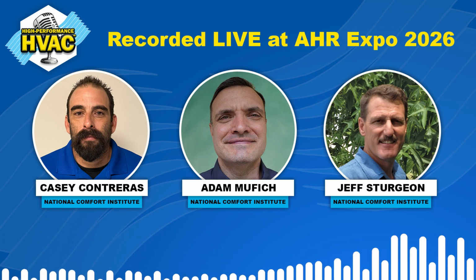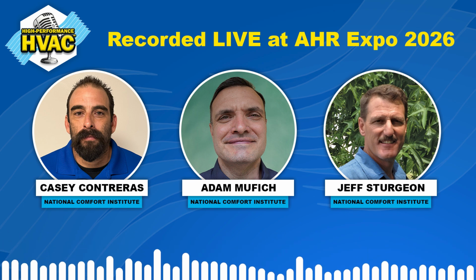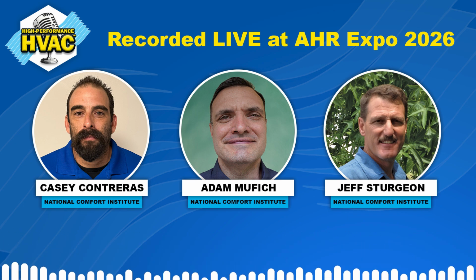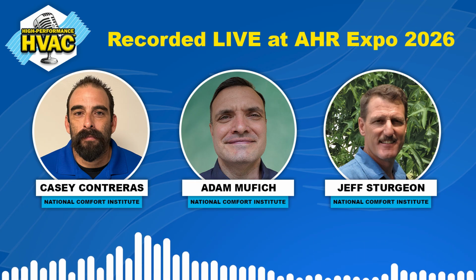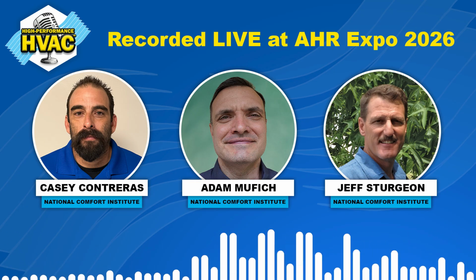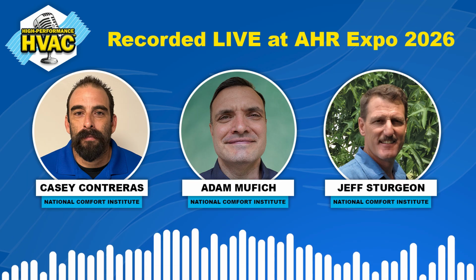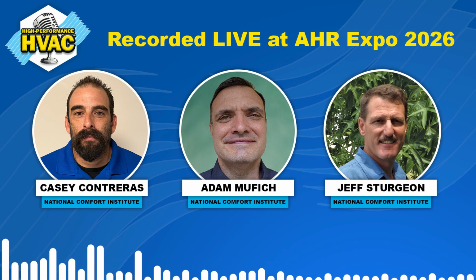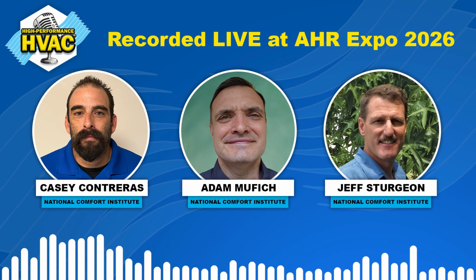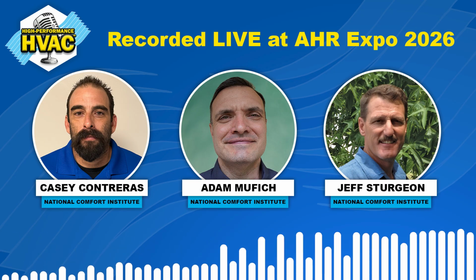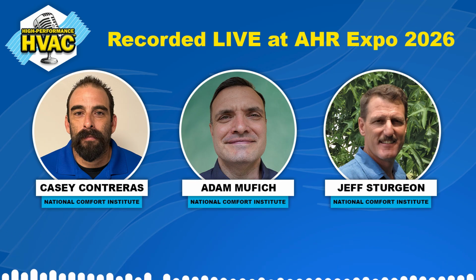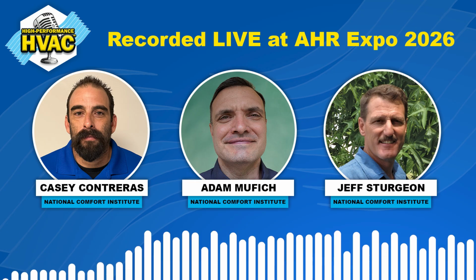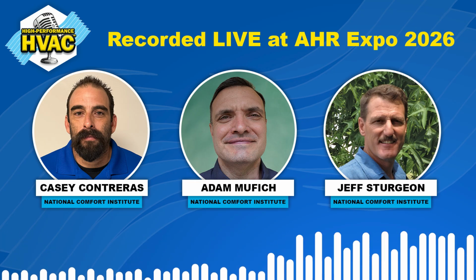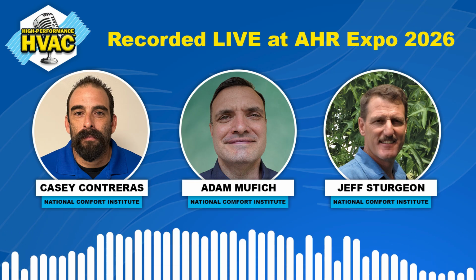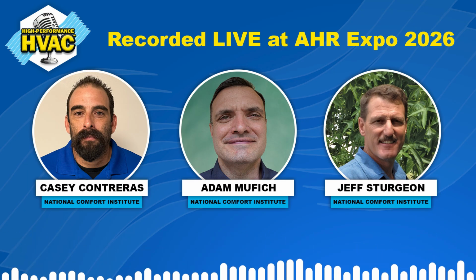Yeah, I remember that restaurant. It was a huge ventilation issue. The restaurant owner's best friend and neighbor told them that swamp cooler on the roof wasn't doing any good, so they shut it off. That was actually the designated makeup air unit for the six exhaust fans in that restaurant. That's the importance of economizers. Once we had that building set up in the kitchen area with the cooktops, there was no air conditioning, just makeup air and exhaust.